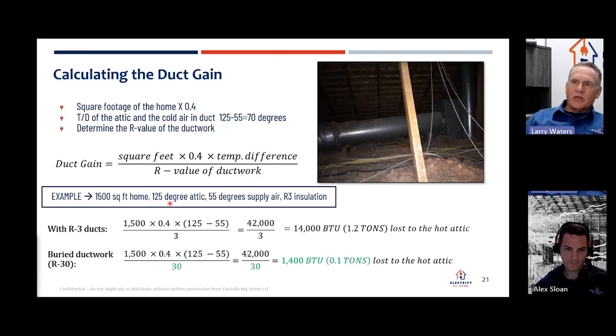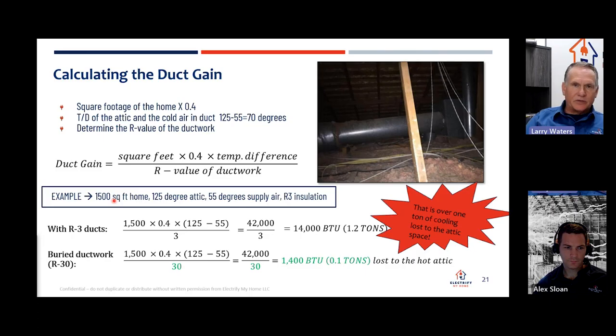So if we bury the ductwork, say let's replace the ductwork, let's lay it down low, let's do a nice job, seal it up, pull it tight so we have as little duct material in the attic as possible. We bury that ductwork with R30 insulation so that we get a good burial around the sides and about 3 inches on the cap, at least around everything. We're obviously not going to be able to bury an 18-inch return air or a 16-inch duct totally, so this is an average. If we bury everything in R30, we're only going to lose 1,400 BTUs. So that's 0.1 tons lost to the attic. So just by burying our ductwork in this 1,500 square foot home, we're able to save 1 ton of cooling capacity, right? Over 1 ton of cooling capacity lost to the attic space.